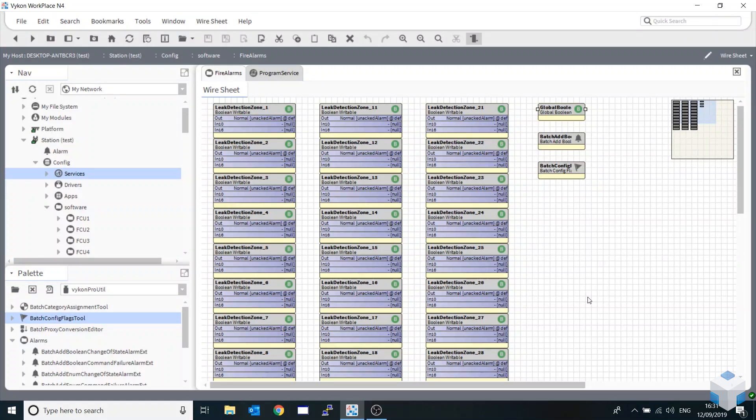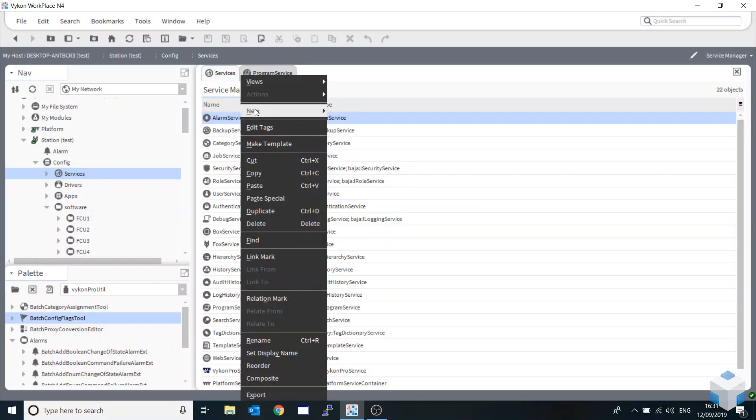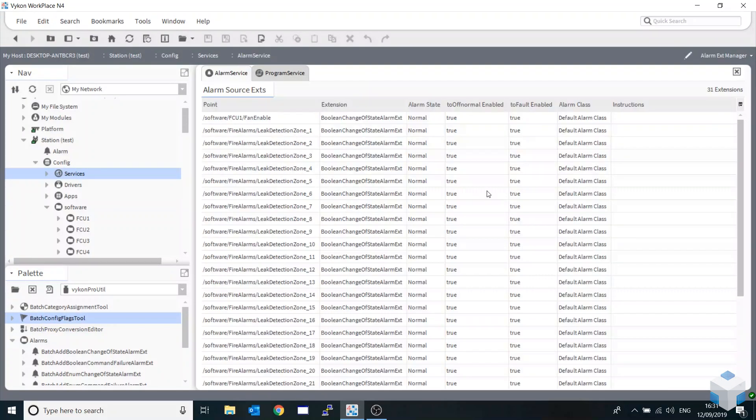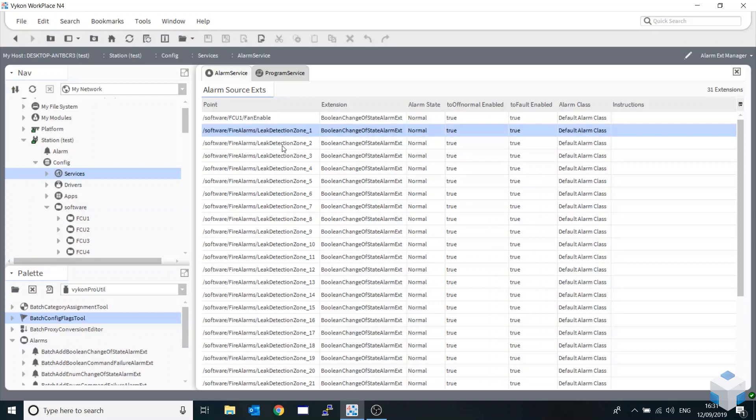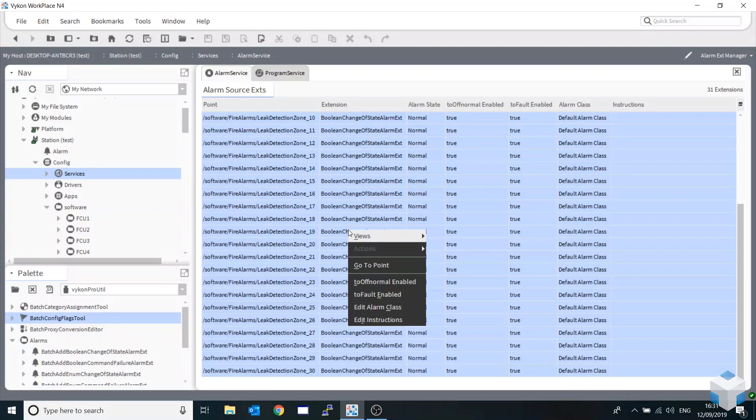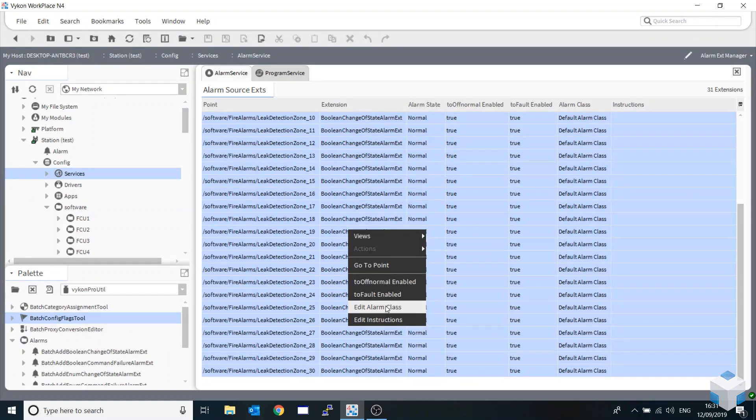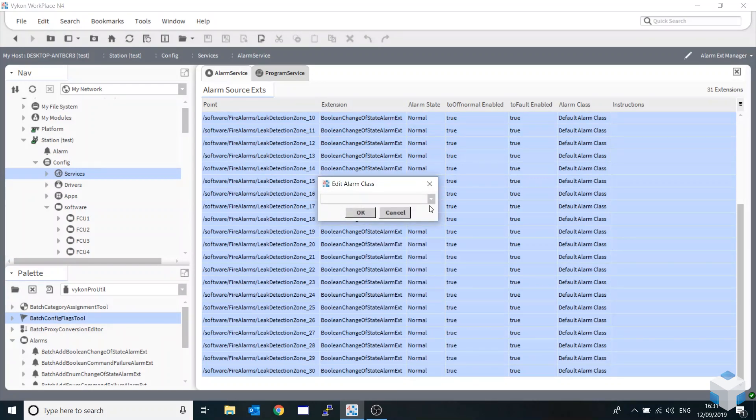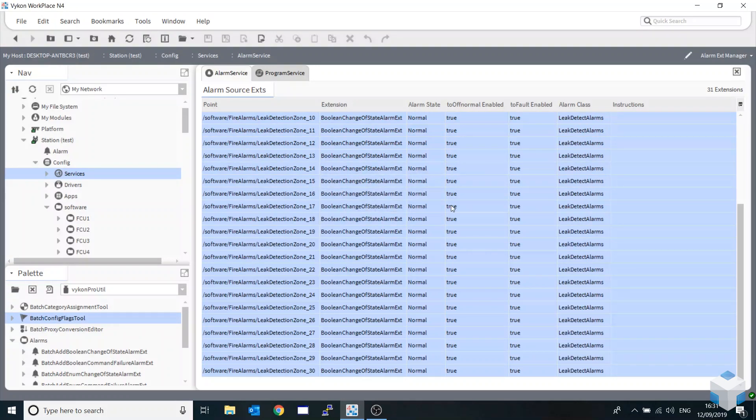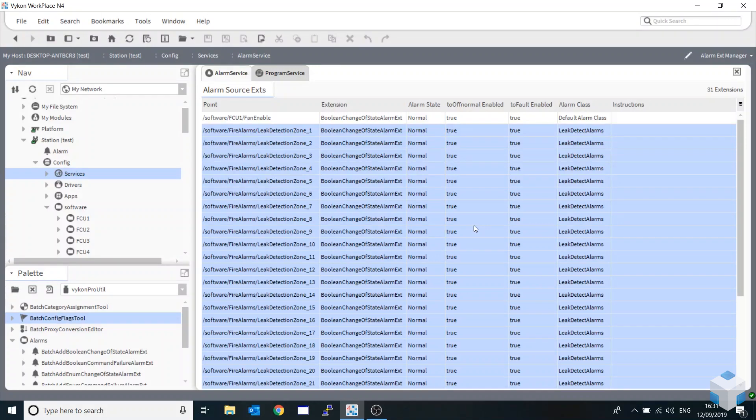I'm going to go back into my services and right click on my alarm service. I'm going to do a view extension manager. This goes out and finds all the points that we've got with an alarm point on. They're all pointed to default alarm class. I'm just going to click them and right click edit alarm class, drop down, and go to a different alarm class. Very quickly on mass been able to change all my alarms across the system. You can actually choose which ones you want - you don't have to do them all. You can cherry pick and use certain ones that you can send to certain alarms. It just shows things very quickly.